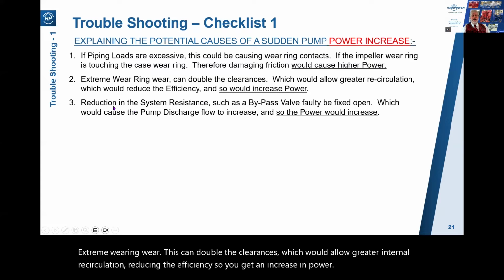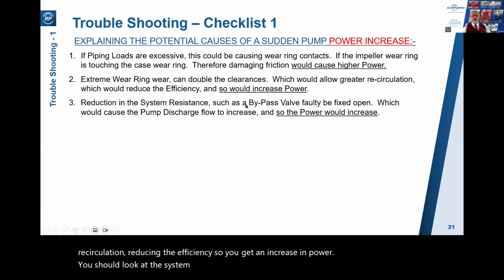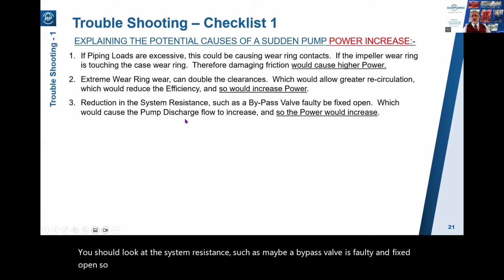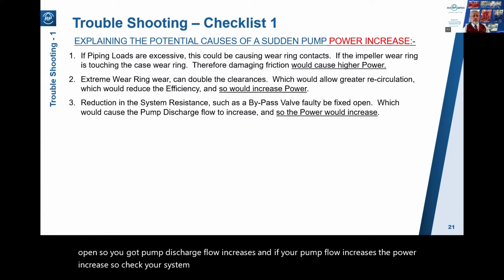You should look at the system resistance, such as maybe a bypass valve is faulty and fixed open. So you've got pump discharge flow increasing, and if your pump flow increases, the power would increase. So check your system resistance curve.